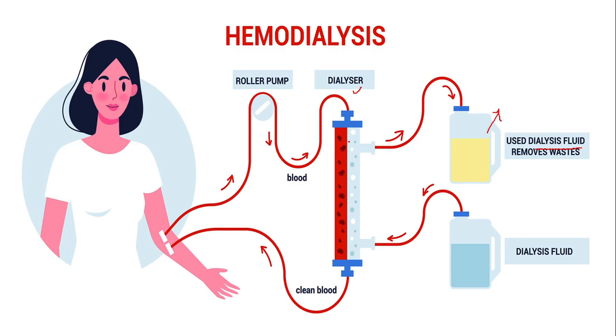The dialyzer is a cylinder that is separated by a membrane, and that membrane mainly performs the function of a semi-permeable membrane. As you know, the semi-permeable membrane allows some molecules to pass through it but not all. This membrane in the dialyzer will allow small molecules such as urea or potassium that are present in excess amount in our blood to pass through, but it will not allow proteins, amino acids, or lipids that are present in our blood to pass out.